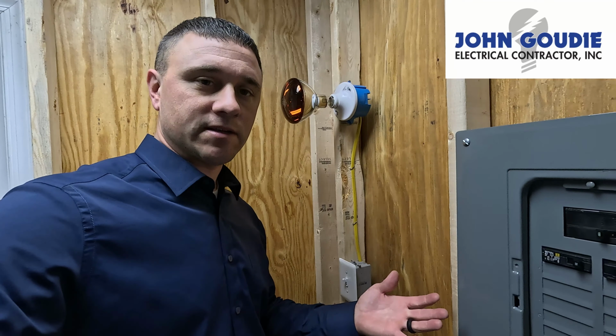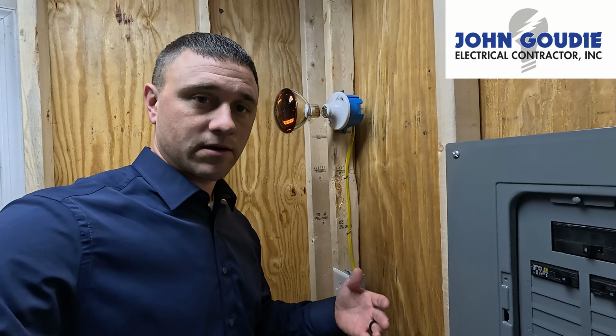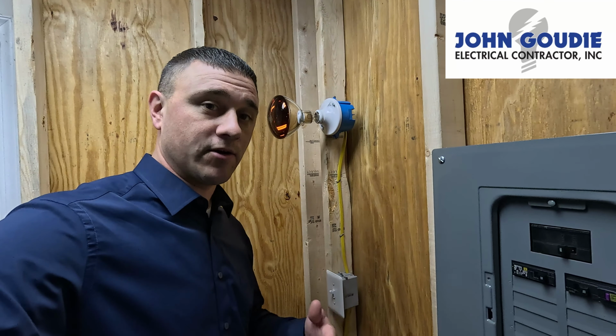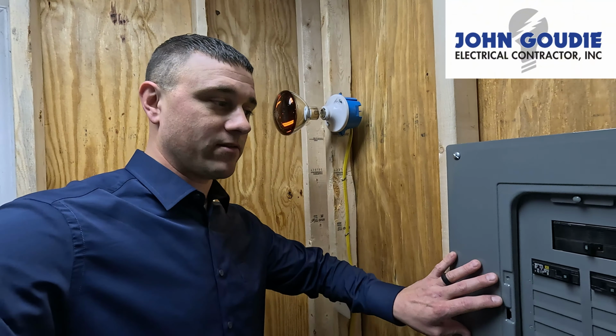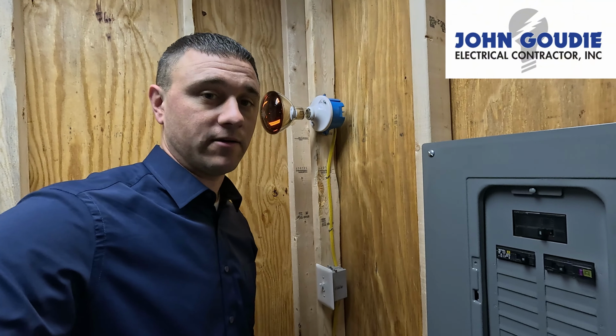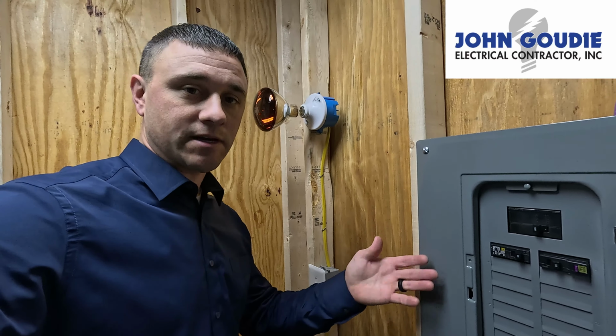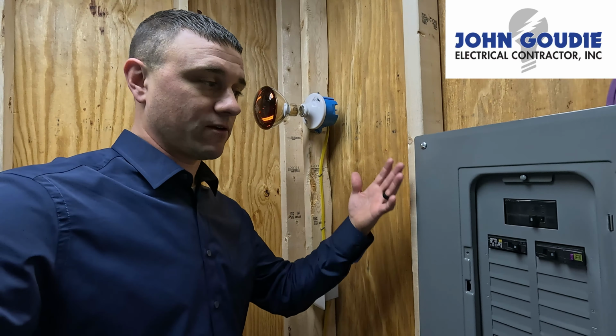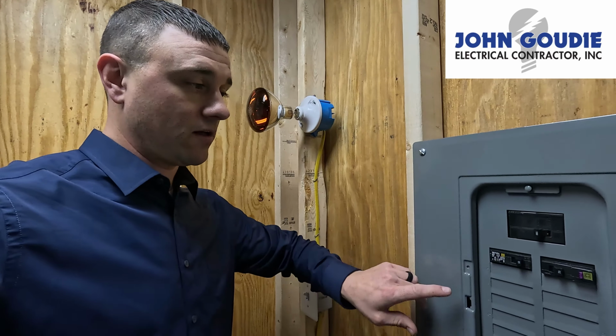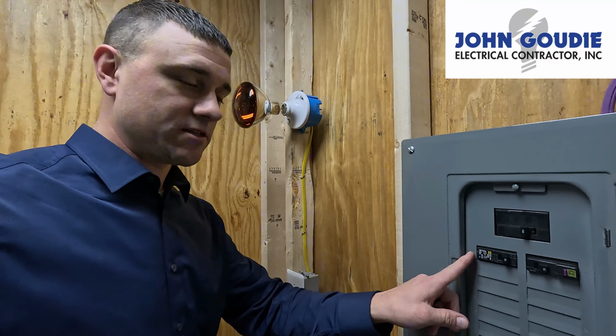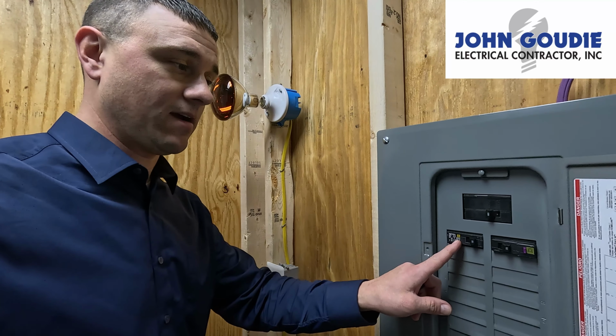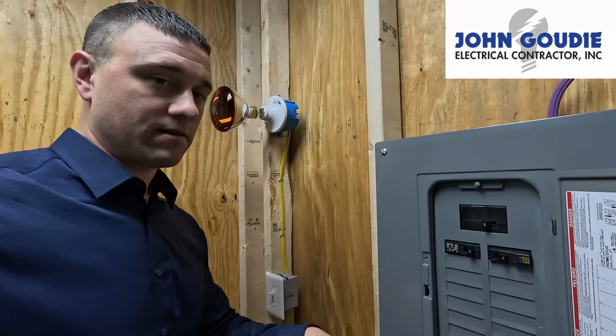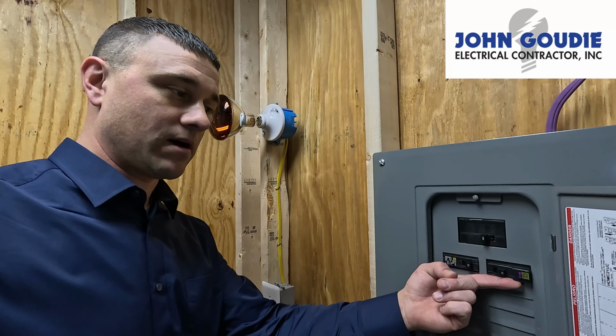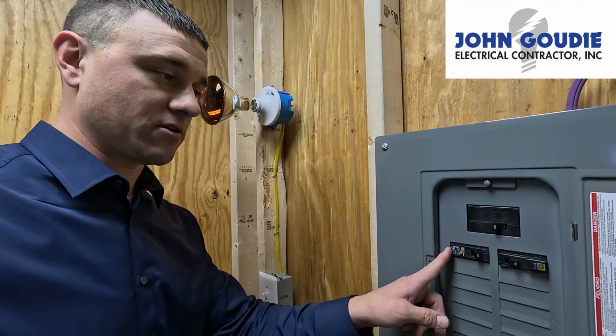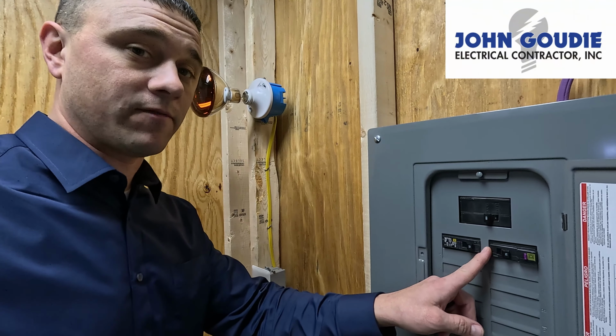So if you've dealt with us in the past, you're probably accustomed to us giving you a good, better, best option when we're giving you a price to replace your electrical panel. In the good option, you most likely find the replacement of your panel and all of the breakers with a normal, just miniature circuit breaker, which you see right here. But in the best option, instead of the normal miniature circuit breakers, we're going to have what's called an arc fault breaker.